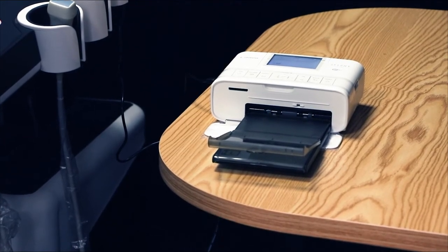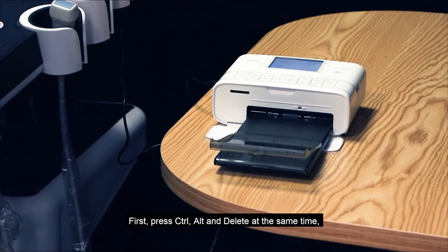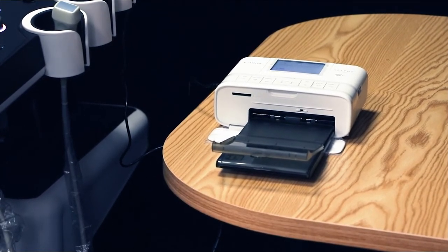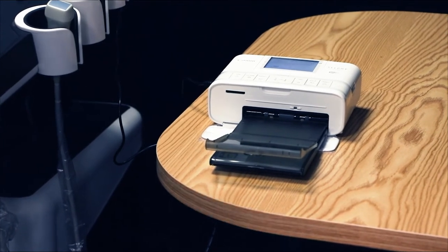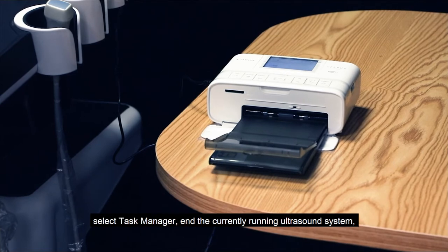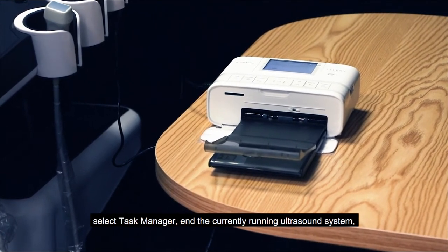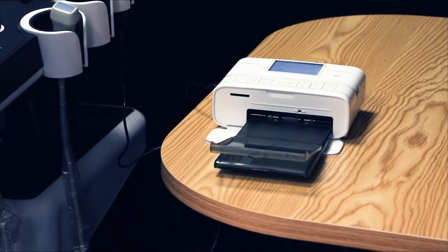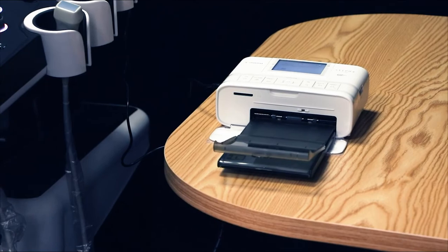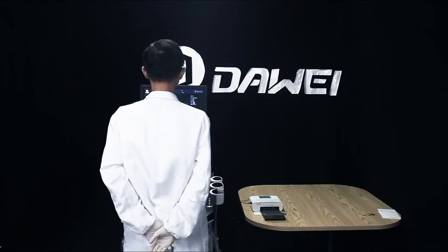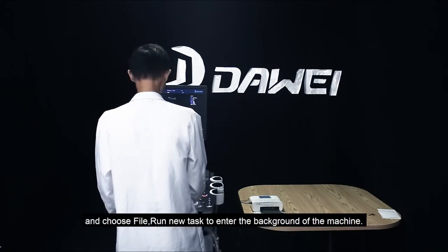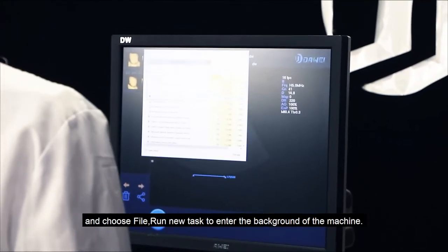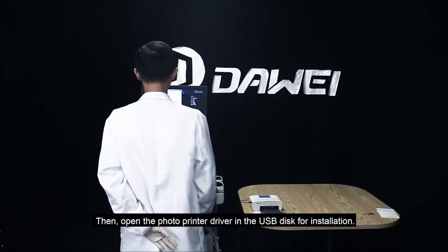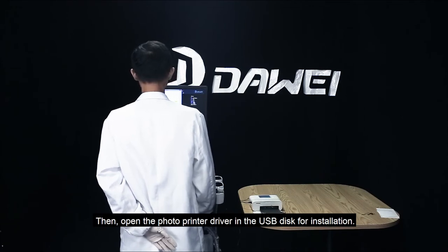Photo printer. First, press Ctrl, Alt, and Delete at the same time. Select Task Manager, end the current running ultrasound system. And choose File, Run New Task to enter the background of the machine. Then, open the photo printer driver in the USB disk for installation.